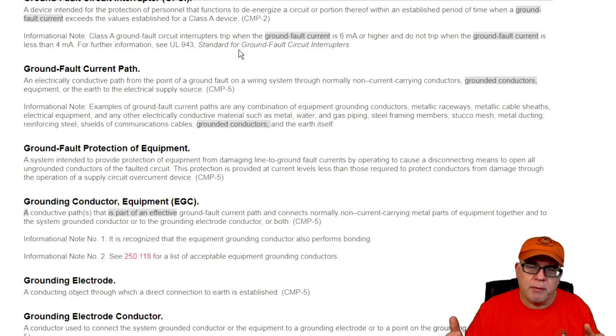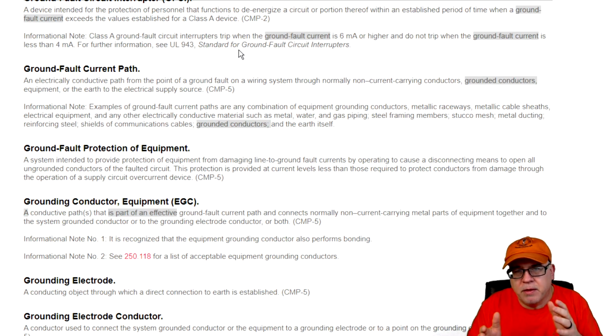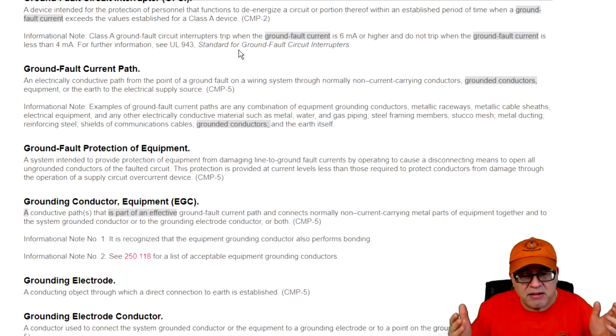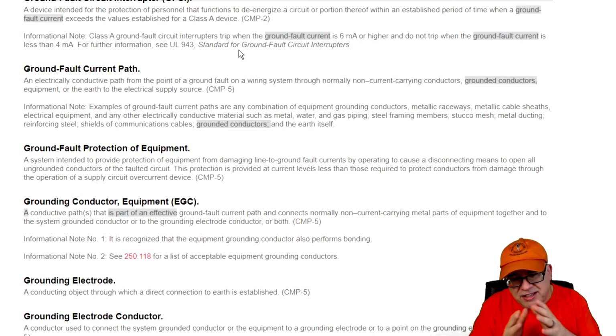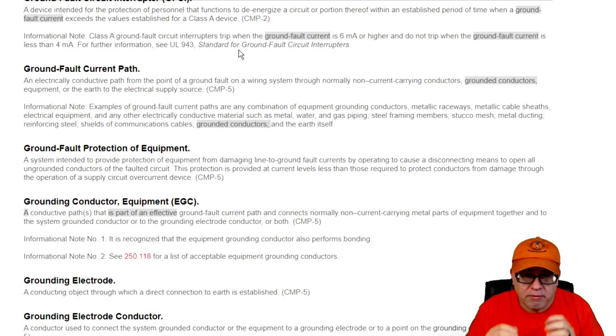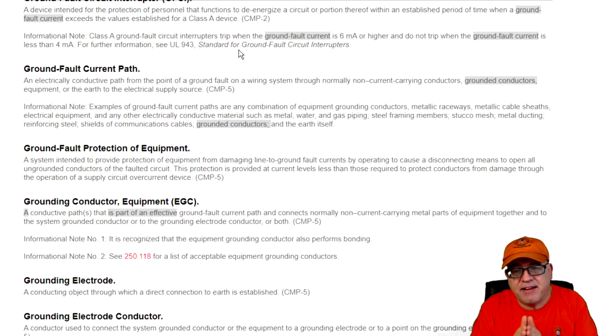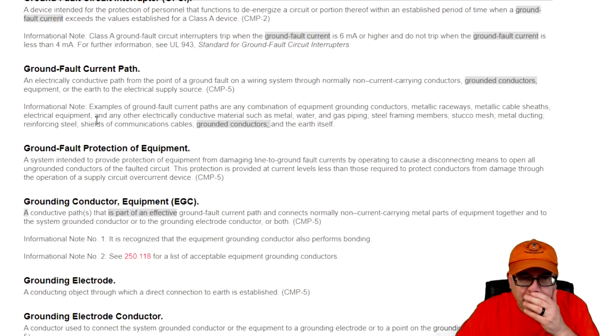So you hear us all talk about 5 milliamps because it's right there in the middle. So 5 milliamps nominal. So anything over 5, designed to trip. Anything that is less than 4, it's not supposed to do anything, okay? So we all call it that, but to be very technical, it is 6 milliamps or higher will trip, 4 milliamps or lower will not trip, okay? Again, we just call it 5 milliamps because it's right there in the middle. That's your threshold, so that's what we refer to.